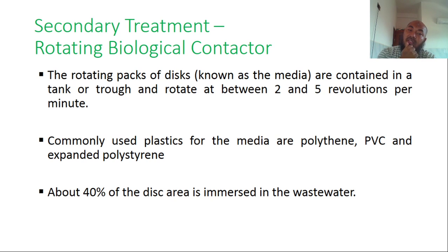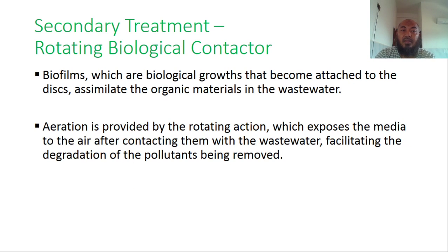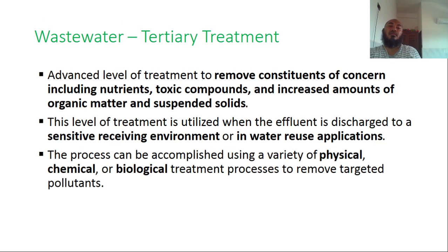About 40% of the area is submerged in the wastewater. Biofilms, which are biological growths that become attached to the disc, assimilate the organic material in the wastewater. Aeration is provided by the rotating action, which exposes the media to the air after contacting them with the wastewater, facilitating the degradation of the pollutants being removed.